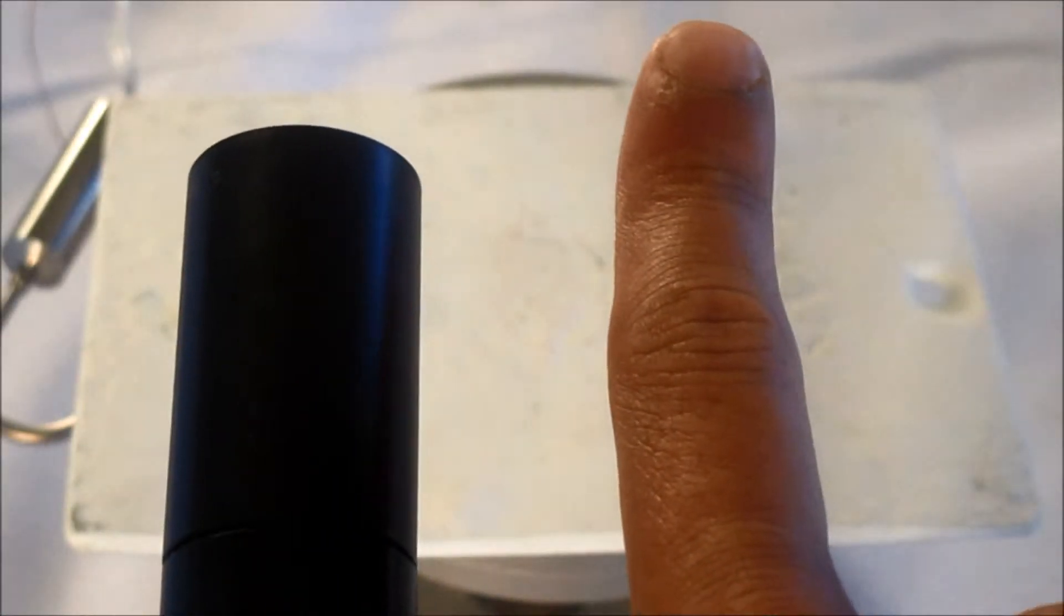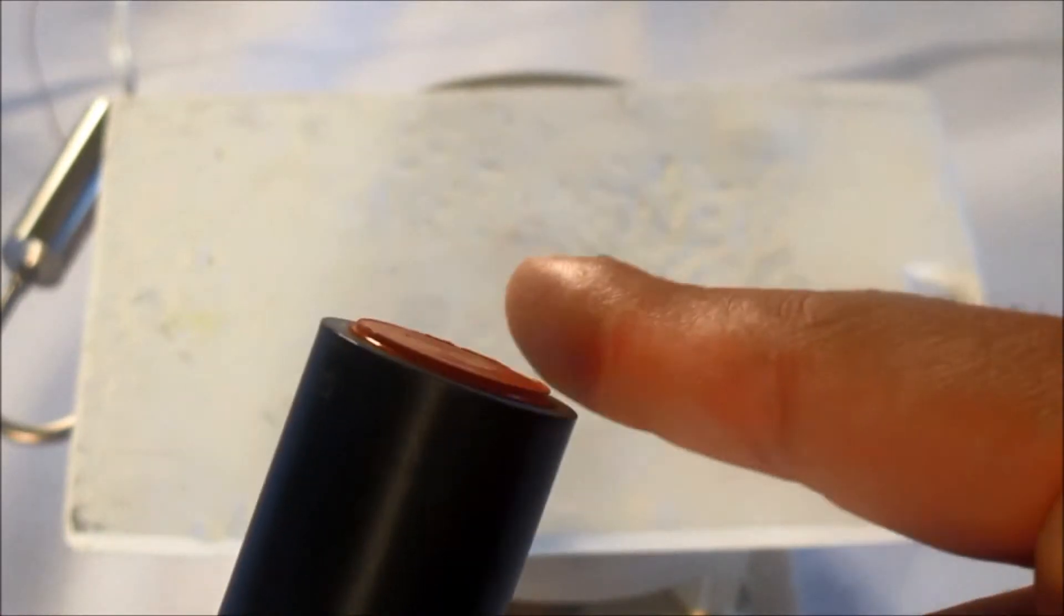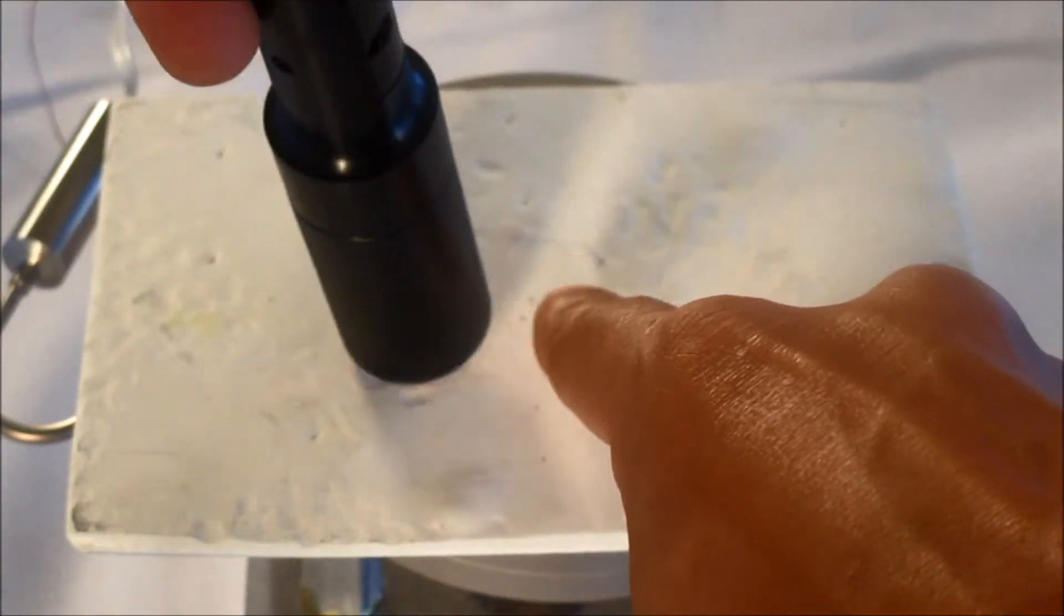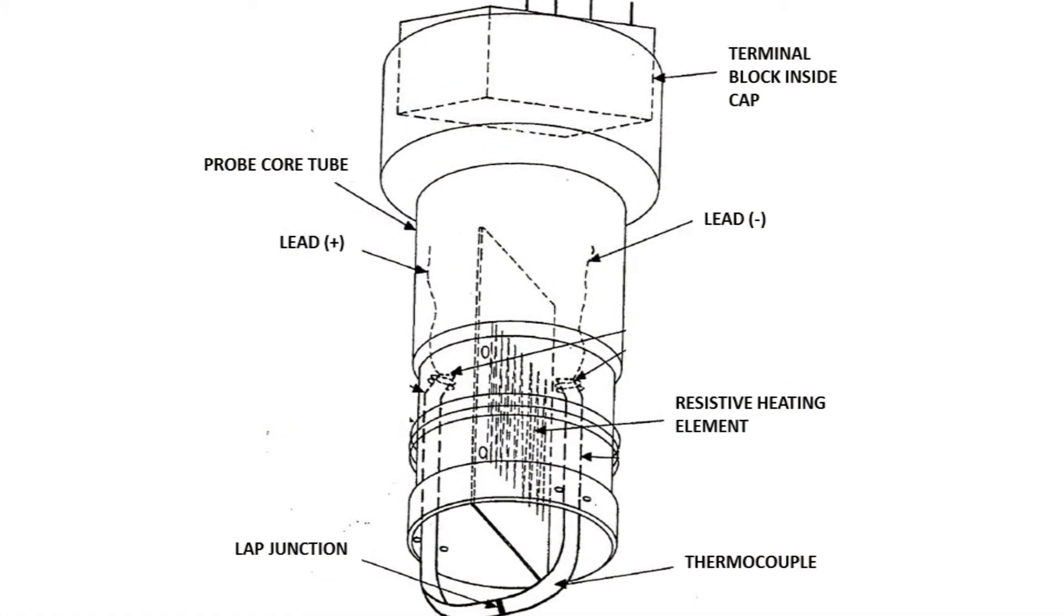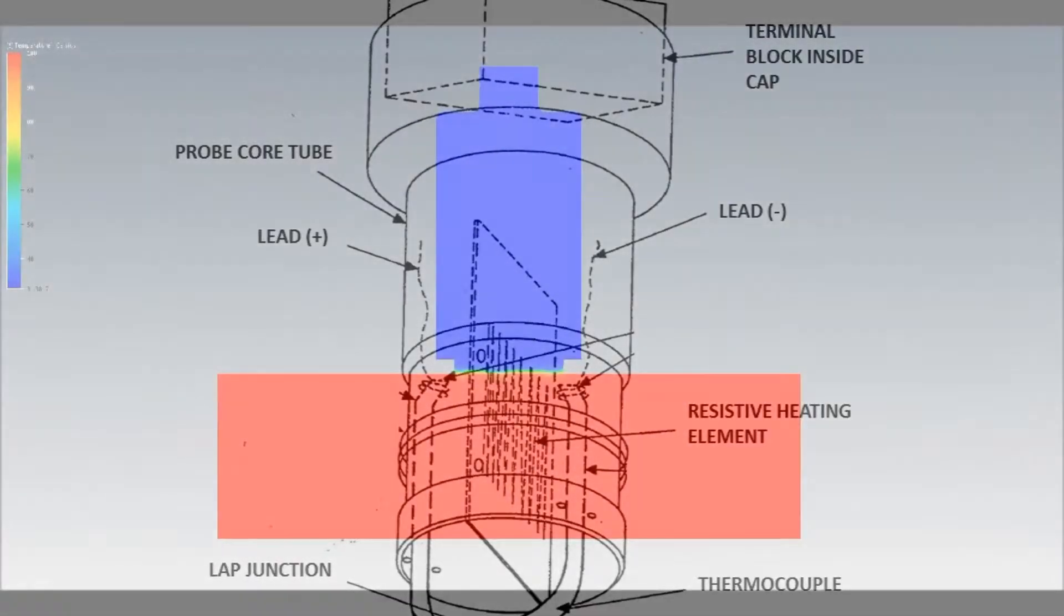The key feature of our device is a specially designed probe that replicates the thermal response of a human finger. We've achieved this by using a material with human-like thermal properties, simulating human body temperature, and precisely positioning the probe's internal components.